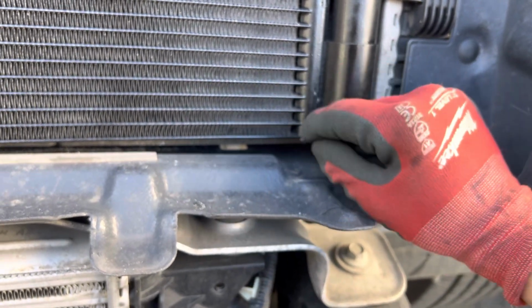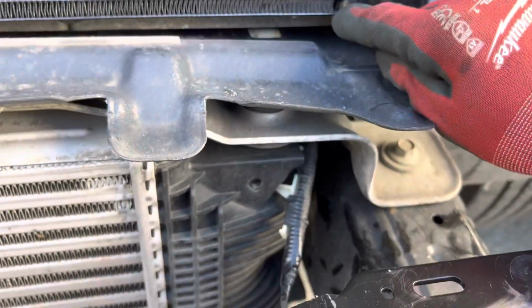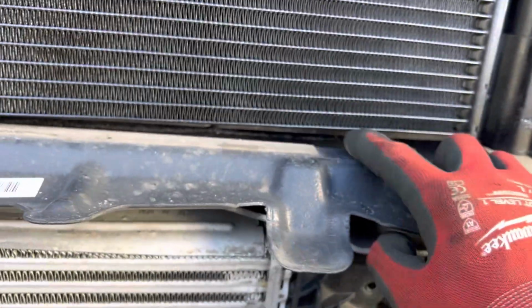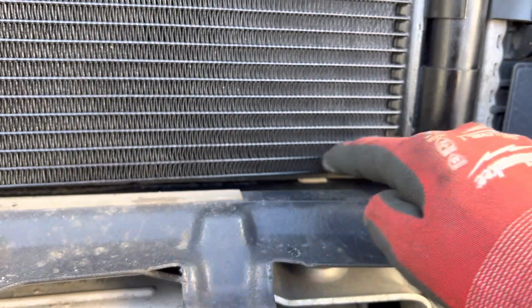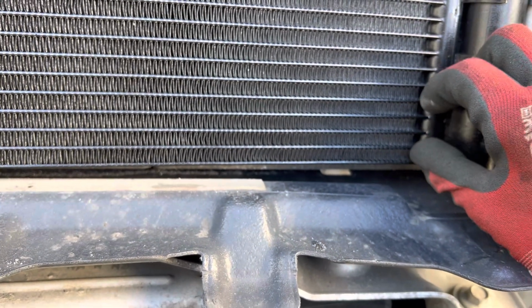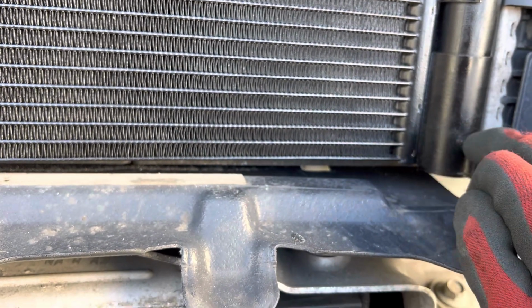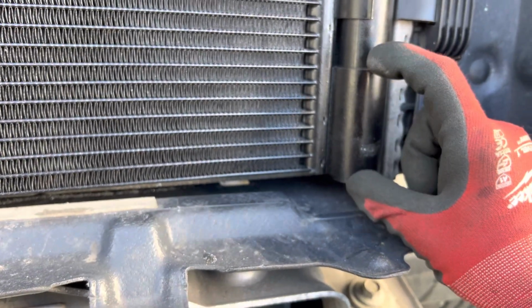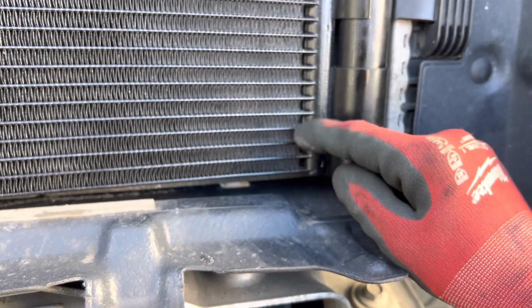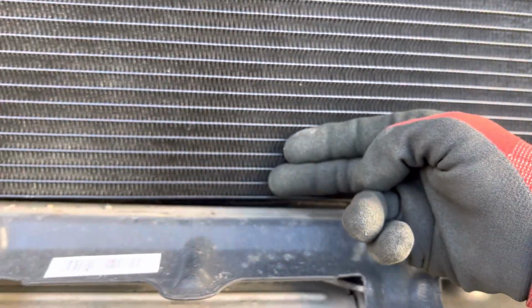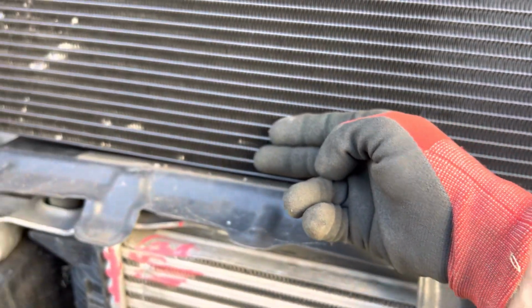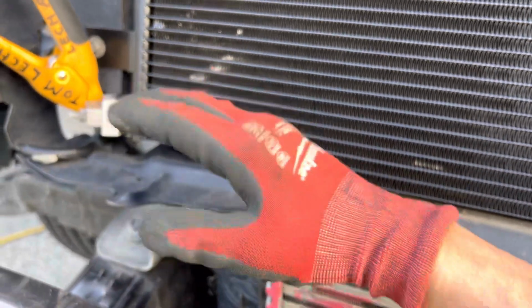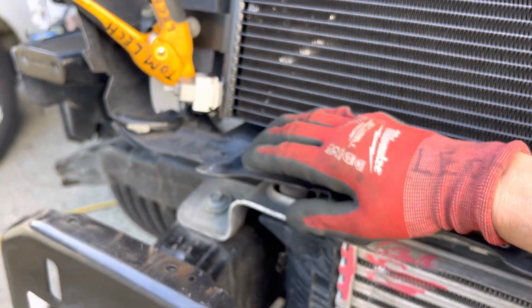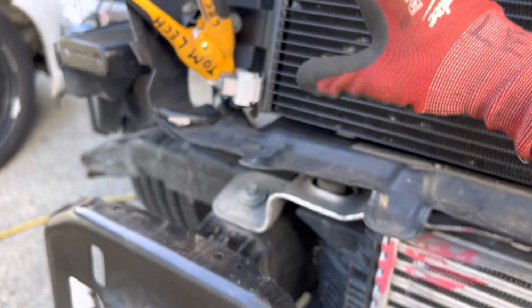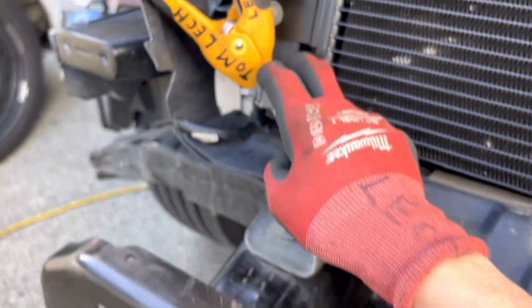There's a hole down here, and only this last one way down here, that's a solid piece of metal. That's not a fin. I mean, that's not a tube. That's a solid piece of metal. But this is a tube, and the next one's a tube. So these 3 or 4, there's a little hole cut down in the bottom of here. This is filled with liquid. And so the liquid and the oil are only going through these last few tubes. And this is getting subcooled right here. This is doing the subcooling of the condenser. It's all liquid. It's getting the last BTU possibly out of that liquid. So it's rejected its energy. It's rejected the heat, and it comes out here cooler.